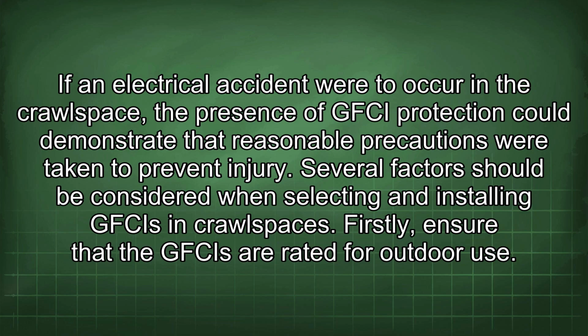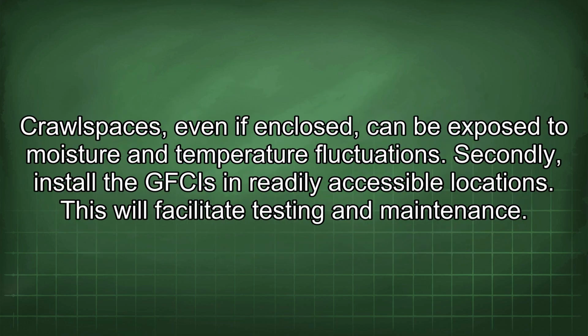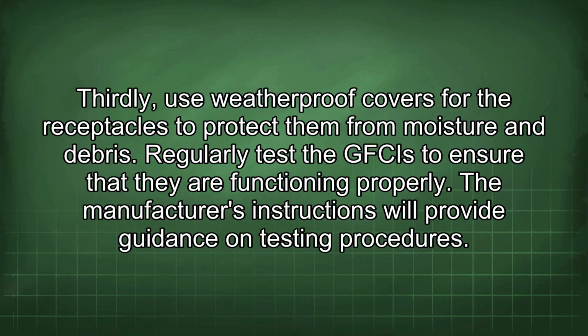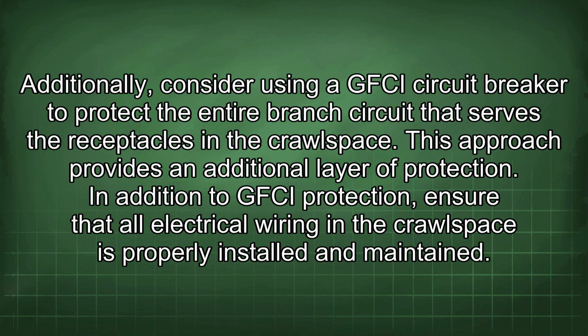Several factors should be considered when selecting and installing GFCIs in crawlspaces. Firstly, ensure that the GFCIs are rated for outdoor use. Crawlspaces, even if enclosed, can be exposed to moisture and temperature fluctuations. Secondly, install the GFCIs in readily accessible locations. This will facilitate testing and maintenance. Thirdly, use weatherproof covers for the receptacles to protect them from moisture and debris. Regularly test the GFCIs to ensure that they are functioning properly. The manufacturer's instructions will provide guidance on testing procedures. Additionally, consider using a GFCI circuit breaker to protect the entire branch circuit that serves the receptacles in the crawlspace. This approach provides an additional layer of protection.